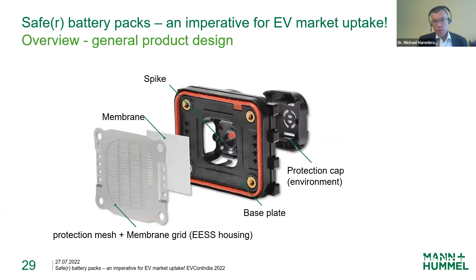So this is how those systems can look like. The active component here is the membrane. This is normally mounted - this is the battery system, this is the environment. Just remember there's a spike here in the base plate, and I will explain the function. If we have a malfunction, so one battery cell starts to vent, the pressure inside the battery pack is increasing. So the membrane is pushed towards the outside and then gets into contact with this pin. And this pin then ruptures the membrane.